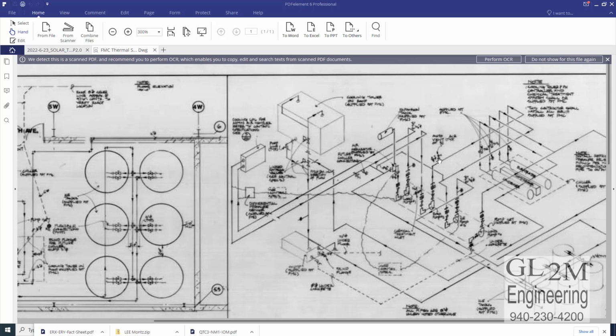These are air vents, obviously. You can see those everywhere. This is your differential pressure sensor at a typical cooling coil, and it is driving the variable frequency drive, which is speeding or slowing up the pump. And here's an expansion tank. This is another critical ingredient, along with an air separator.